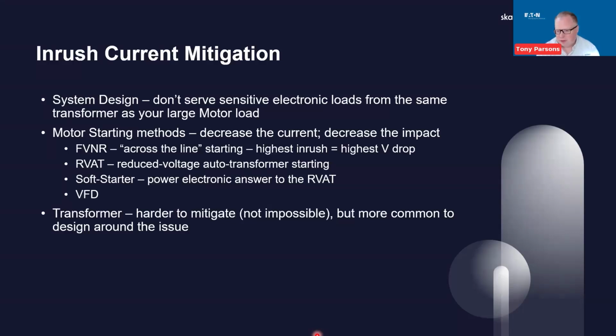With transformers, when you energize a transformer, you also have inrush current as well. It's a little harder to mitigate. We don't have soft starters necessarily for transformers. More common, probably, is to design around the issue and make sure things like your relay settings are set to accommodate whatever inrush levels you may expect.